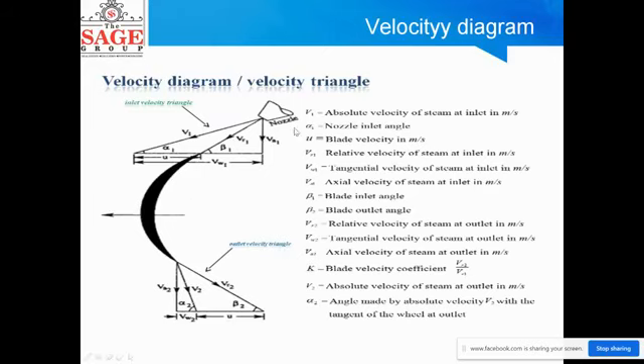Velocity diagram: Steam from the nozzle strikes the blade at velocity V1. V1 is the absolute velocity of steam striking the blade. Vr1 is the relative velocity of steam at the inlet, and U1 is the velocity of the blade. Vw1 is the whirl component and alpha1 is the nozzle angle at inlet. At the outlet, Vr2 is the relative velocity of steam after passing through the blade, V2 is the absolute velocity, and U is the same blade velocity. These are the main velocity components used in the velocity diagram of a steam turbine.